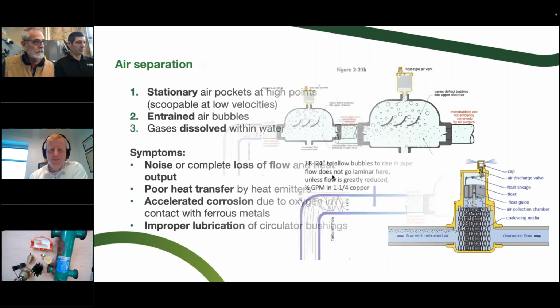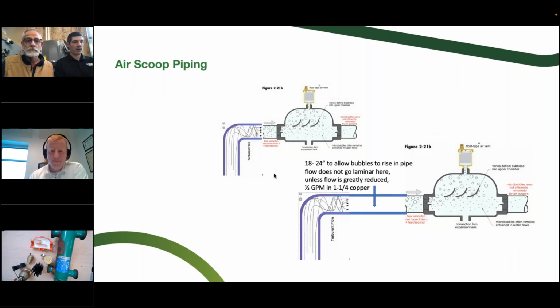For sure. Okay, so let's talk about piping related to an air scoop as well. Can I put a 90 right on the edge of an air scoop? Is that a good practice? As you can see in the picture, not really. They used to say, depending on the size of the air scoop, 18 to 24 inches of straight pipe going into it. That way, you get a chance for the bubbles to start to separate and go to the top of the pipe as they get in there. If you're right at an elbow, you've got a little bit of turbulence coming around that elbow, especially if you're over pumping the system, which can happen, so the water is not separating its air before it gets into the scoop. So that straight pipe on the front end of it helps the performance a little bit.